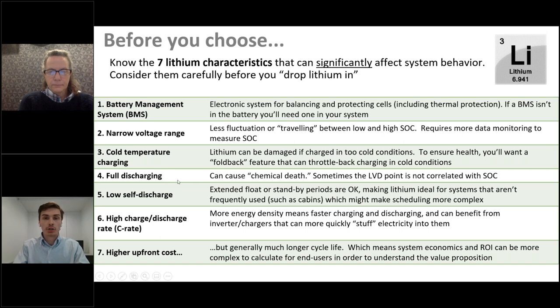For full discharging, we recommend an 80% depth of discharge for 6,000 cycles. Full discharging at 100% every time is obviously going to affect your life cycles more than doing an 80% depth of discharge. That said, if you're using our battery in an emergency power application, maybe you can do a 90% depth of discharge to get maximum battery power, since they won't be cycling it every day, only using it during outages.